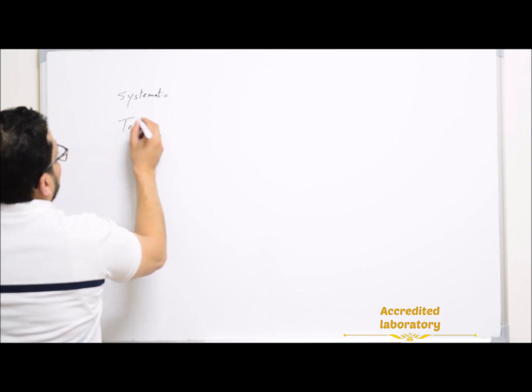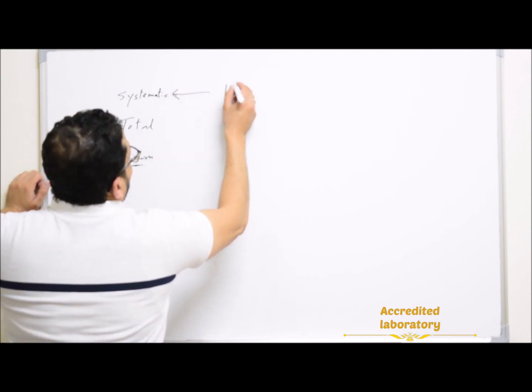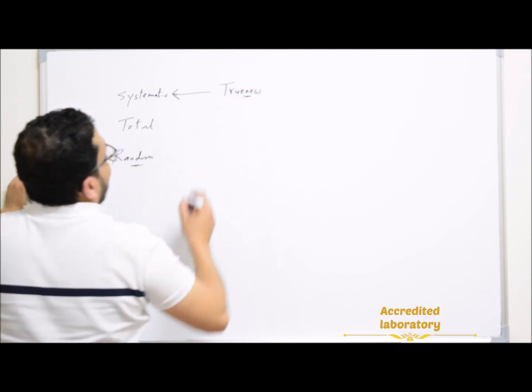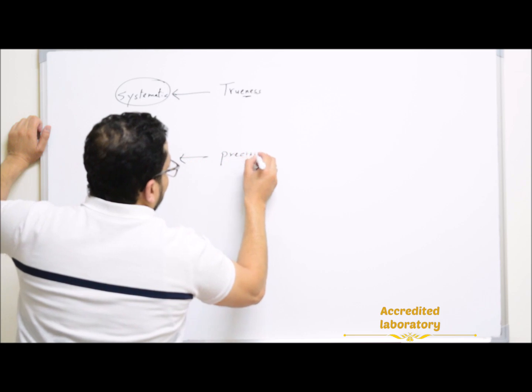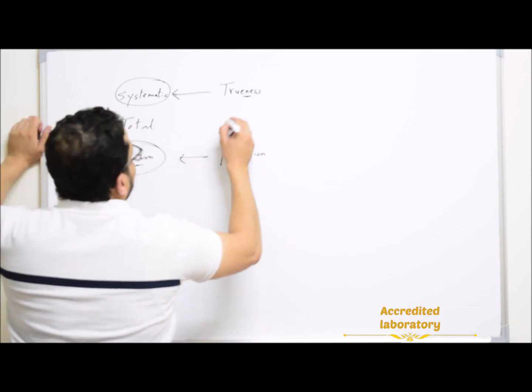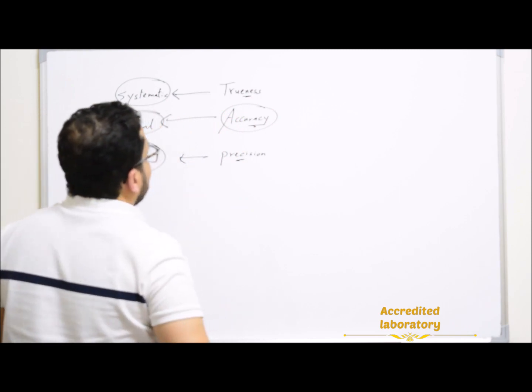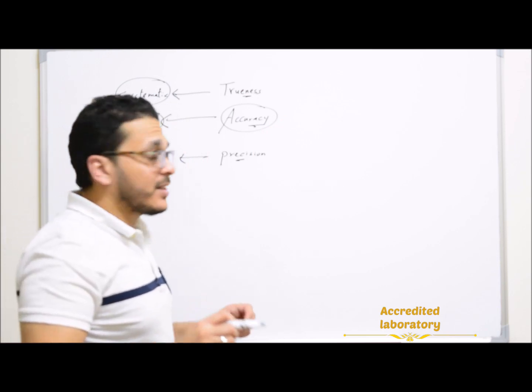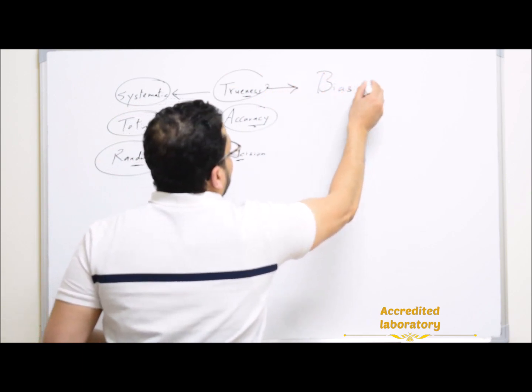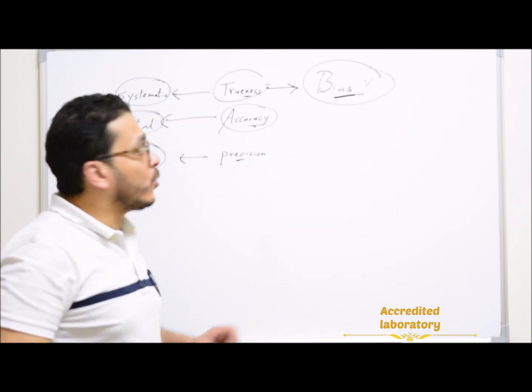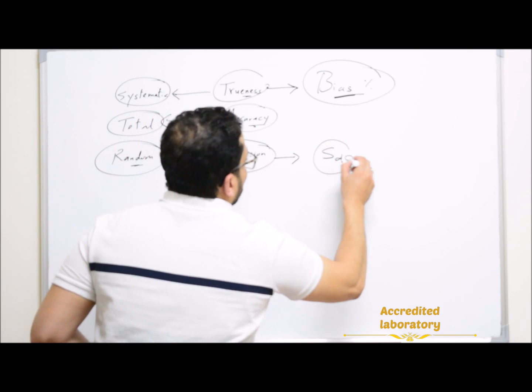Systematic, total, and random errors. Trueness will be the estimate for systematic errors. Precision will be the estimate for random errors. And accuracy will be the estimate of total — both random and systematic — errors, quantified by assessing both. Trueness is expressed as bias percentage, as we explained in the previous lecture how to calculate bias. Precision can be expressed as standard deviation, and this will be our lecture today.